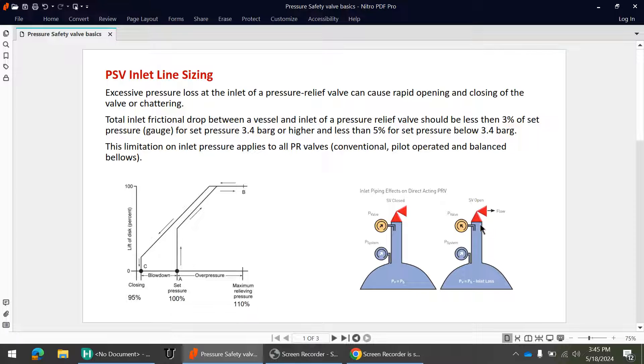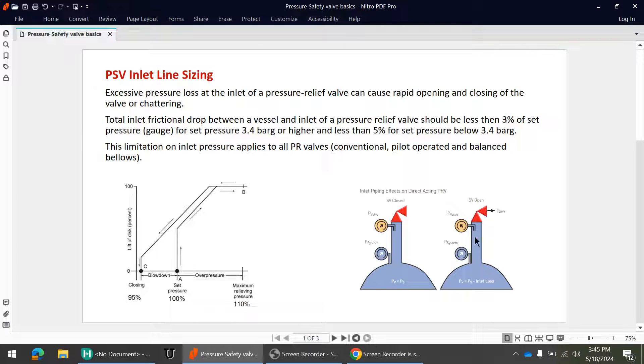As soon as the PSV closes, but the contingency is still ongoing, the pressure will rise again and the PSV will open again. As soon as it opens, there will be pressure loss, the pressure will fall below the reseat pressure, and the PSV will close again — creating continuous cycling. To avoid this, API says the line loss should not exceed 3% so that the PSV inlet pressure does not drop below the reseat pressure.